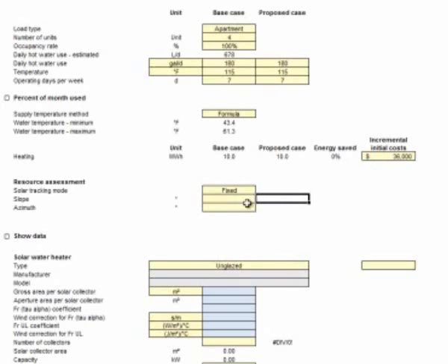What we want to do is come over here. Are we going to have a location? Where is the location going to be? Now, after this video, we're going to come back and look at the location and the wherewithal. But let's just say a good design slope is about 15 degrees plus the latitude that you're at. So in central Illinois, we're at 40.2 degrees of latitude. I add 15 degrees to that. That gives me a total slope of 55 degrees.